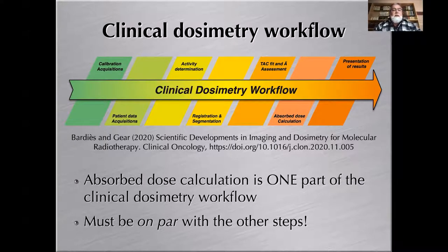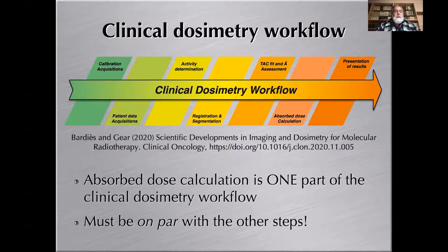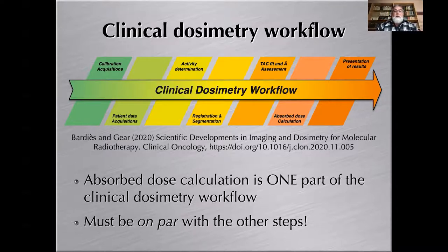The first step is calibration acquisition before patient imaging, which grants the possibility of activity assessment at the patient level. Then there is patient data acquisition, followed by activity determination — meaning reconstruction, but also implementing various corrections to go from counts detected in the image to activity: scatter correction, attenuation correction, partial volume effect correction, and so on. Then comes registration and segmentation of images acquired at different time points after administration of the radioactive drug.